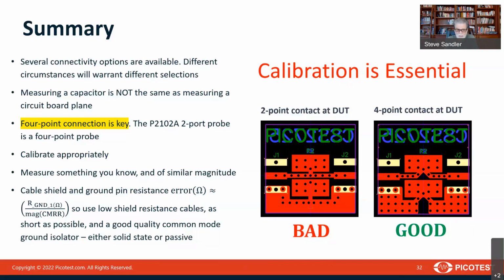Calibration is really tricky. You need to make sure that you do it appropriately. You need to make sure that you do it accurately. In the case of measuring very low impedance, that also means that you have to make sure that you understand the coupling of the probes and get it fixed so that it's not a variation.